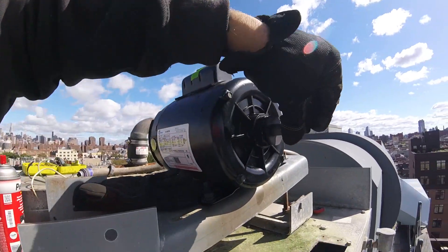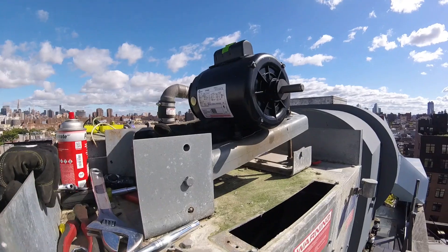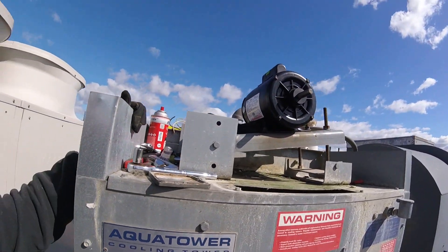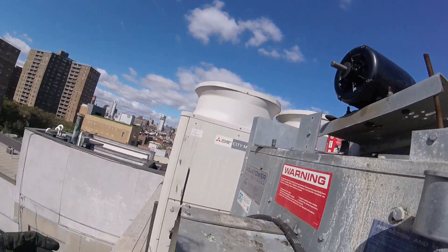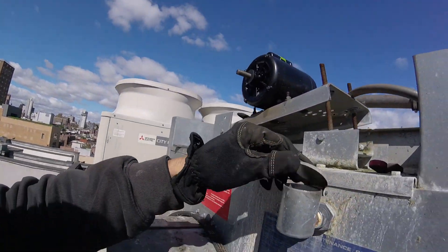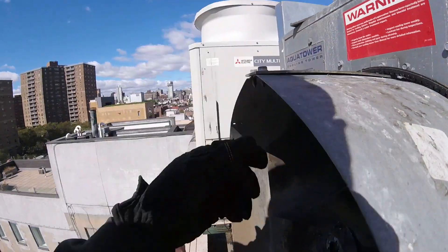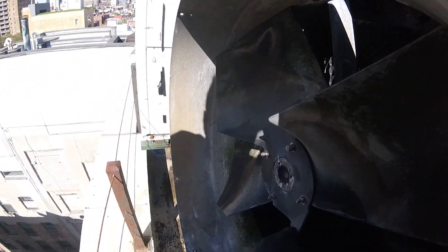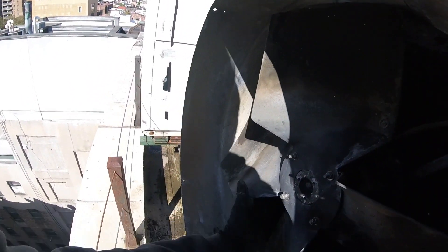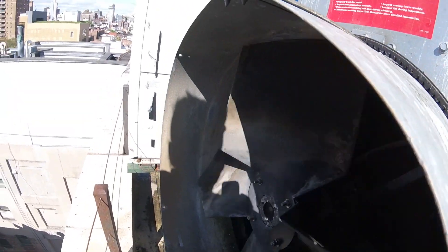This is our shaft. We're going to pick up a new pulley and a new belt — 4L 770. We're going to pick up something to lubricate; you can see this is very low. We're going to try to lubricate this bearing, and hopefully we can get this going because this thing is freaking rough — this is really bad. Hopefully we can get this going.